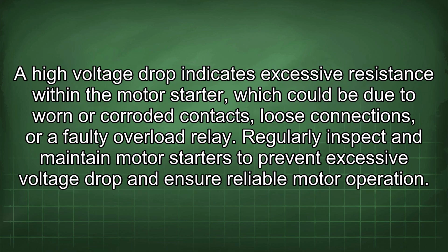A high voltage drop indicates excessive resistance within the motor starter, which could be due to worn or corroded contacts, loose connections, or a faulty overload relay. Regularly inspect and maintain motor starters to prevent excessive voltage drop and ensure reliable motor operation.